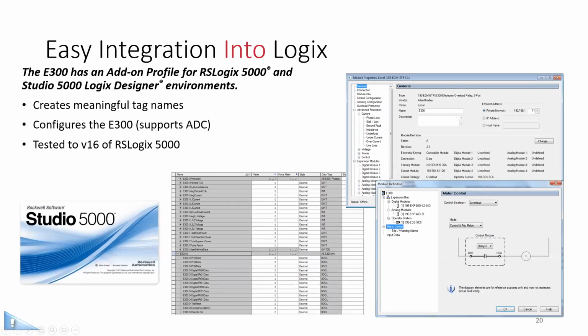So the main communication with the E300 is the Ethernet or the DeviceNet, and it's very easily integrated into your Logix. There's already an add-on profile for RSLogix 5000 and for Studio 5000. The add-on profile creates meaningful tag names for digital inputs, relay outputs, diagnostic information, and configuration data.